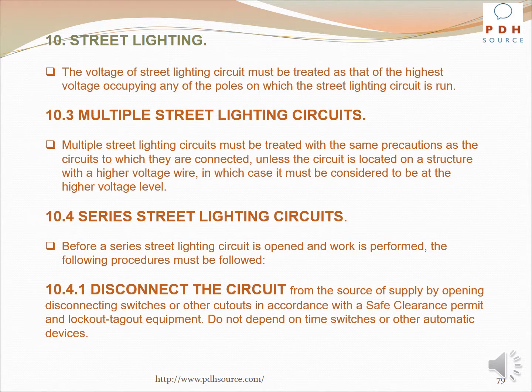The voltage of street lighting circuits must be treated as that of the highest voltage occupying any of the poles on which the street lighting circuit is run. With multiple street lighting circuits, they must be treated with the same precautions as the circuits to which they are connected, unless the circuit is located on a structure with a higher voltage wire, in which case it must be considered to be at the higher voltage level.